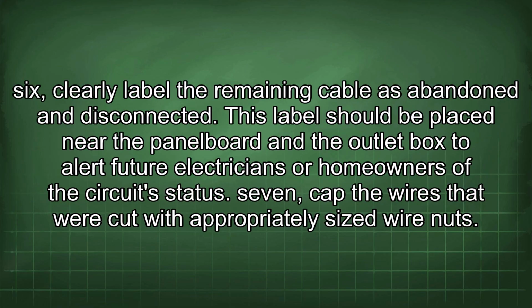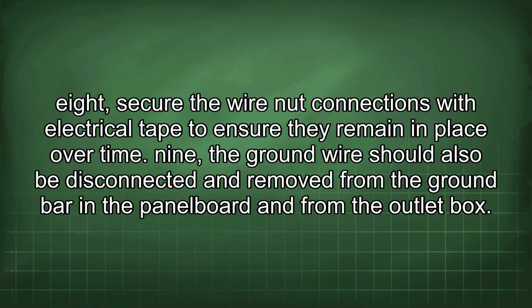6. Clearly label the remaining cable as abandoned and disconnected. This label should be placed near the panel board and the outlet box to alert future electricians or homeowners of the circuit status. 7. Cap the wires that were cut with appropriately sized wire nuts. 8. Secure the wire nut connections with electrical tape to ensure they remain in place over time.